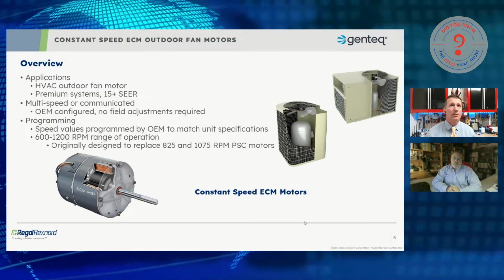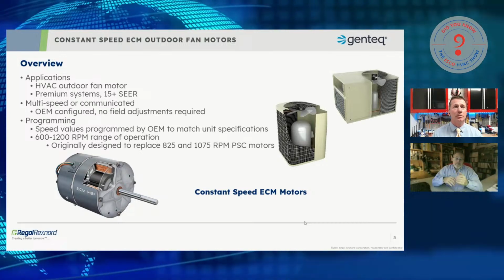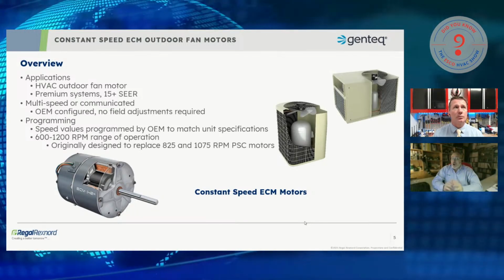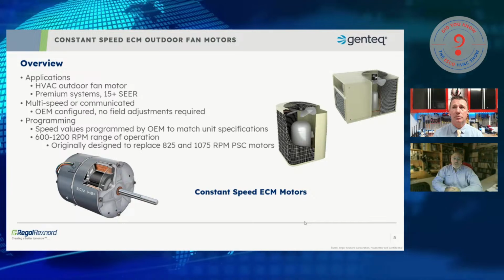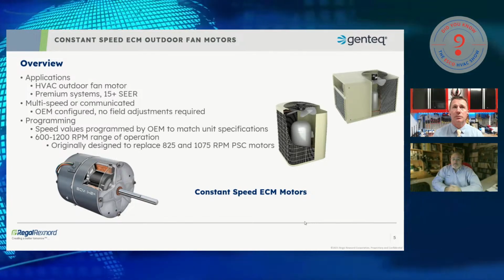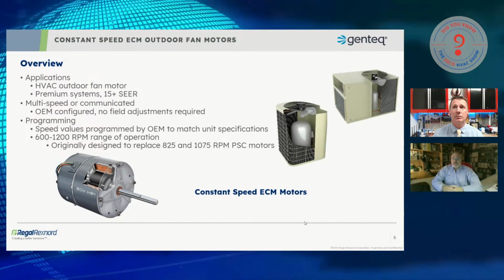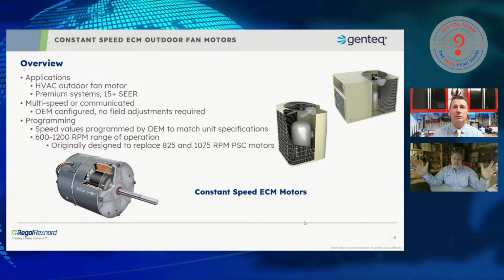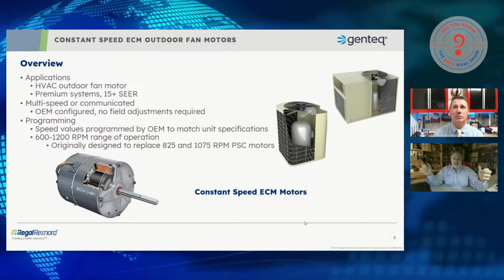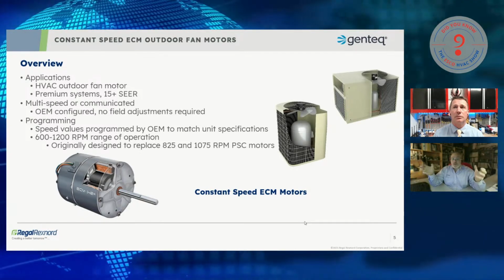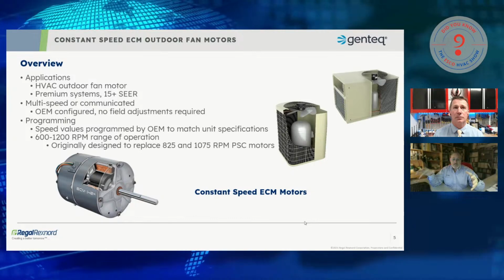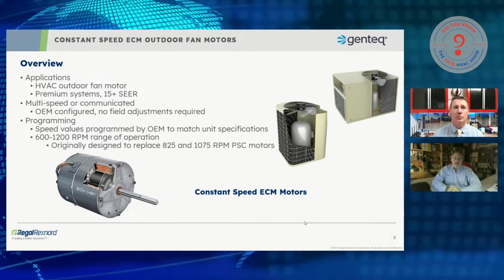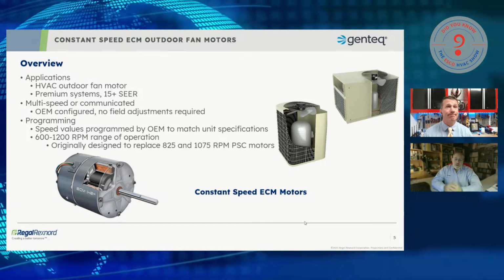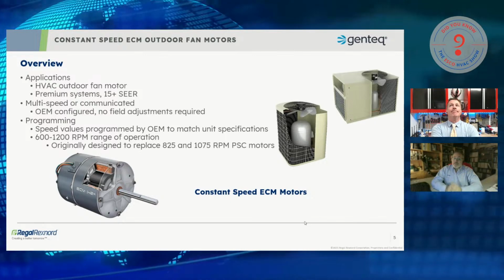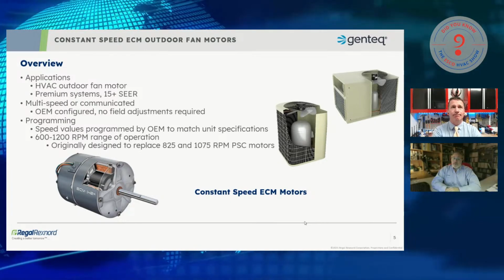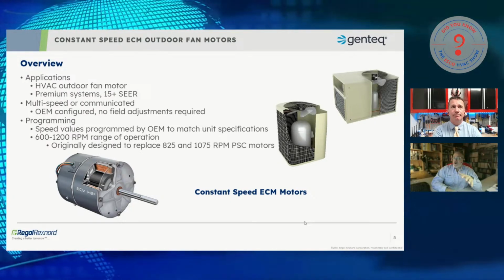Right. They may program that motor to run at 825 or at 1075, or as we're seeing today, they may choose to let the blade engineer develop some kind of blade that's very large and very odd looking, but moves the same airflow at a lower RPM, so we get less decibels, less noise out of the equipment, and then they can program that motor to run at any RPM they want. So they can program that motor anywhere from 600 to 1200 RPM.